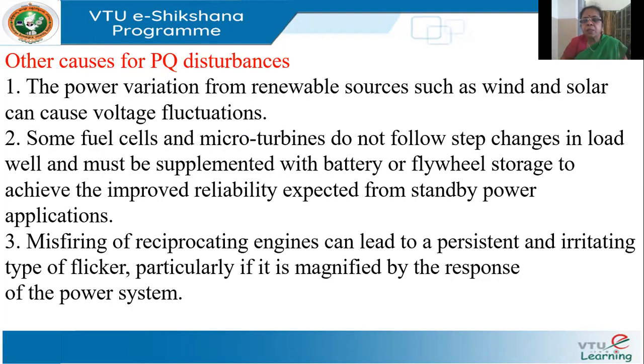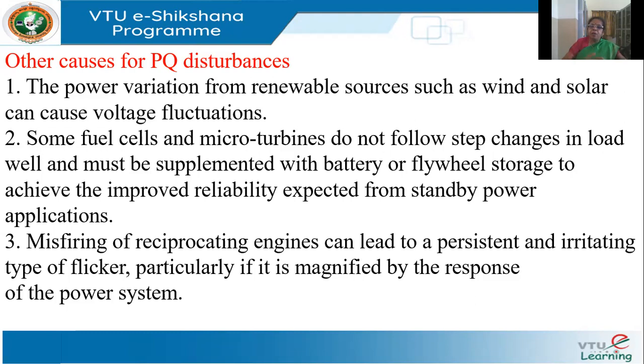There are other causes of concern for power quality. If we use wind and solar technology, which is dependent on the weather, we can have dynamically changing voltages based on varying wind speed or solar irradiation, which can cause voltage fluctuations. Microturbines and fuel cells do not follow a step change in load quickly — the transient period is large and they take time to reach steady state. Therefore, such technologies may have to be supplemented with battery or flywheel storage.